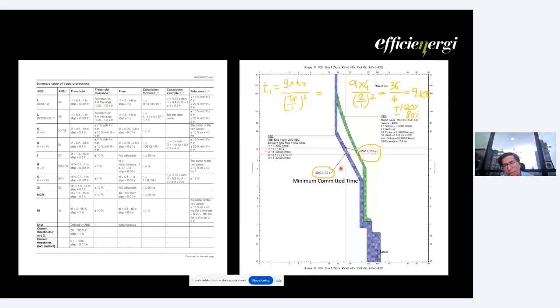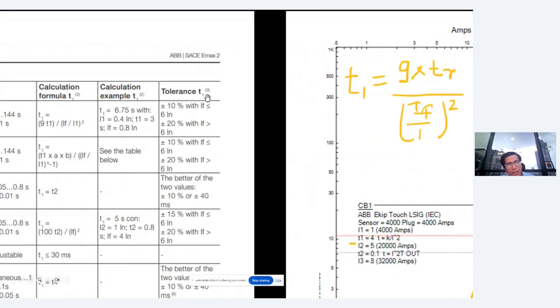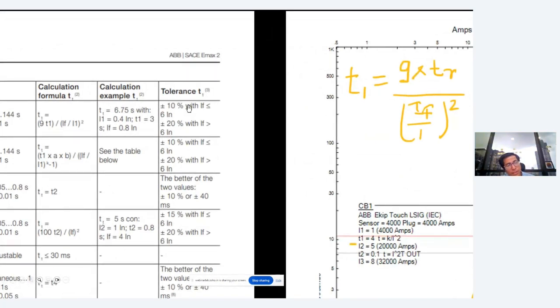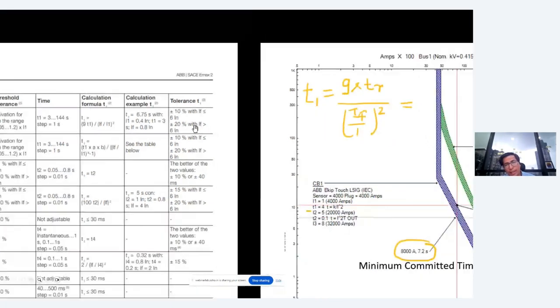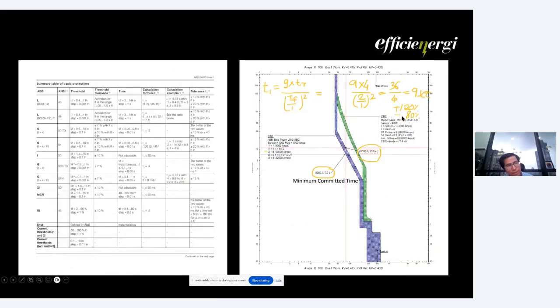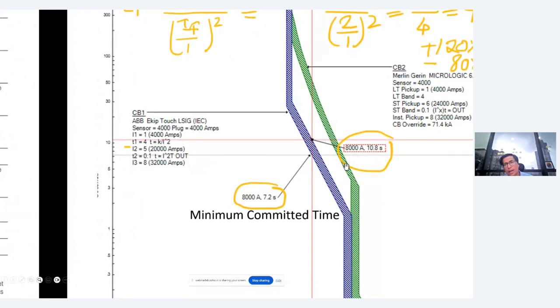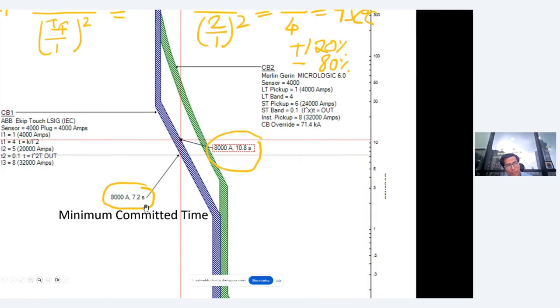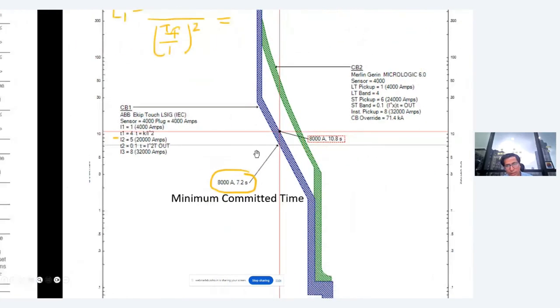But as we know, there is a tolerance of plus minus 20%. Here you can see they have given 10% as the tolerance, but there is also a suffix written over here, that is 3. This 3 means these tolerances apply only if the conditions are as specified by the standard. But on site, the specified conditions are not always there. So normally they take plus minus 20%, irrespective of the conditions, and accordingly this curve is made. So you can see 9 seconds. For 120%, 1.2 times 9 is around 10.8 seconds. And 0.8 times 9 seconds comes to 7.2 seconds. You can clearly see that here.